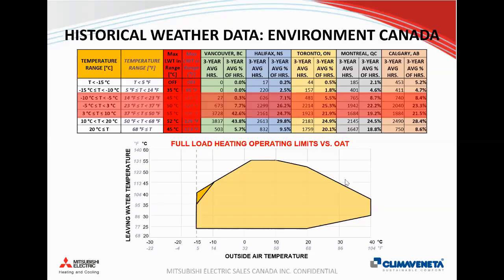There is another class of this type of equipment available from other manufacturers in Canada that typically will have gas injection compressors, so you can achieve a little bit of an extended operating range and operate a little bit lower, like -20. And even at -20, you might be able to achieve a slightly higher supply temperature. But if we just look at the conventional basic type of air-to-water heat pump for commercial settings, we'll see that our minimum temperature that we can operate the heat pump is -15. But also at -15, depending on the specific model that's selected, you can only really get as high as about 40, maybe 45 degrees, depending on the manufacturer, in terms of the supply temperature.